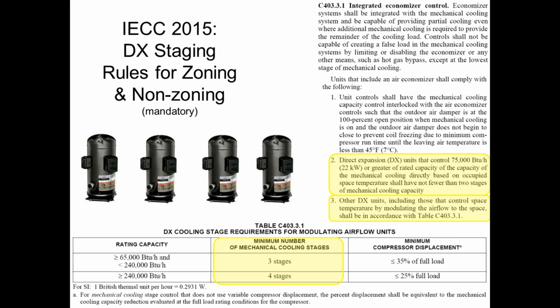When I read those that control space temperature by modulating airflow to the space, I'm thinking zone damper system. If I have a VVT or a VAV zone damper system, the thermostat tells the damper to open more or open less depending on how much cooling it wants, right? So to me, that's controlling space temperature by modulating airflow to the space. So as soon as I hear there's a zone damper system, I'm going to go to 3 stages, or possibly 4 stages if it's a big unit.